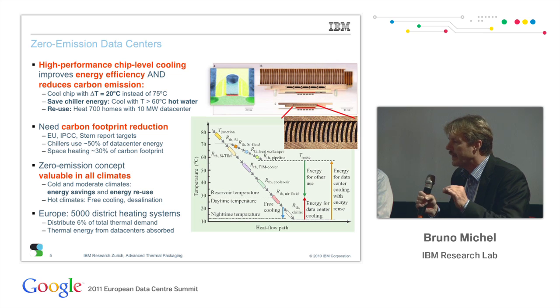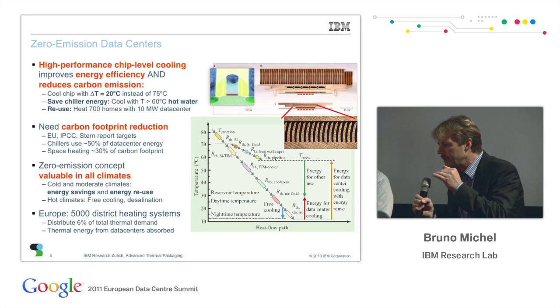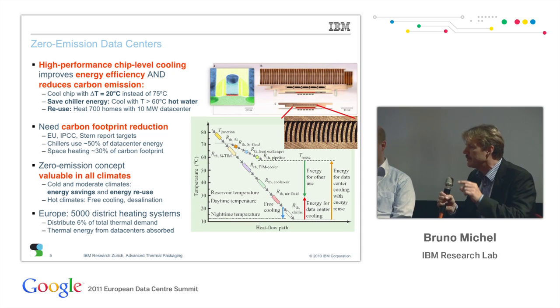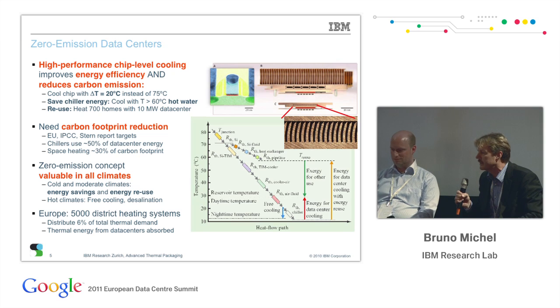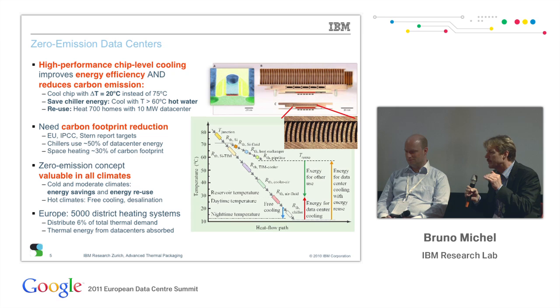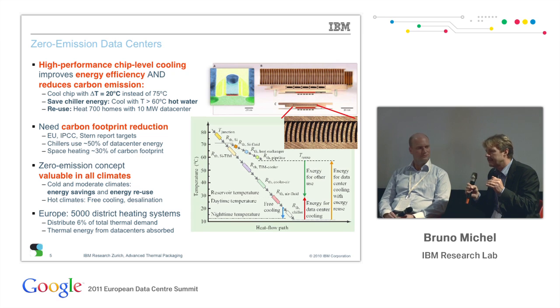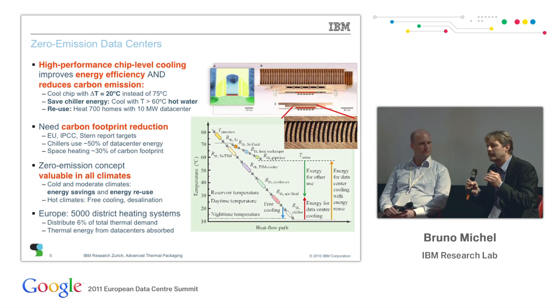In a water-cooled, high-performance water-cooled system where we have the processor directly cooled, we eliminate a lot of thermal resistances and make them smaller. That's the small boxes on the graph there. So we can capture the heat at the 60 degrees C temperature level without having the transistors run hotter. They're exactly at the same temperature. That's why the lifetime will be the same. So we don't want to affect the lifetime.